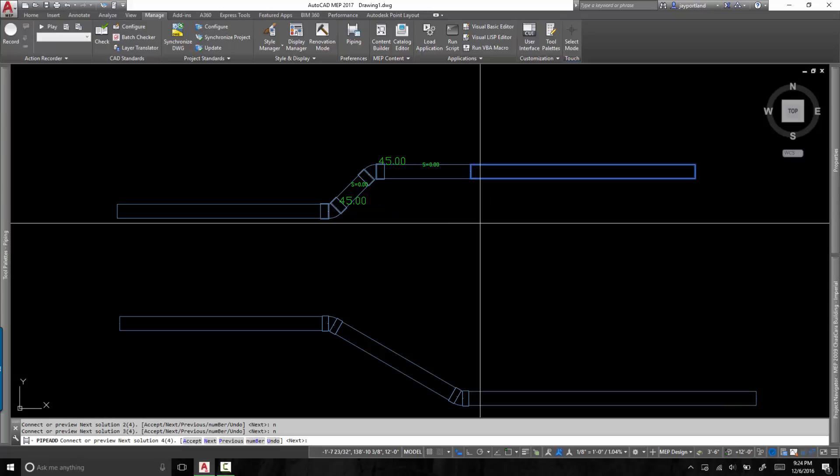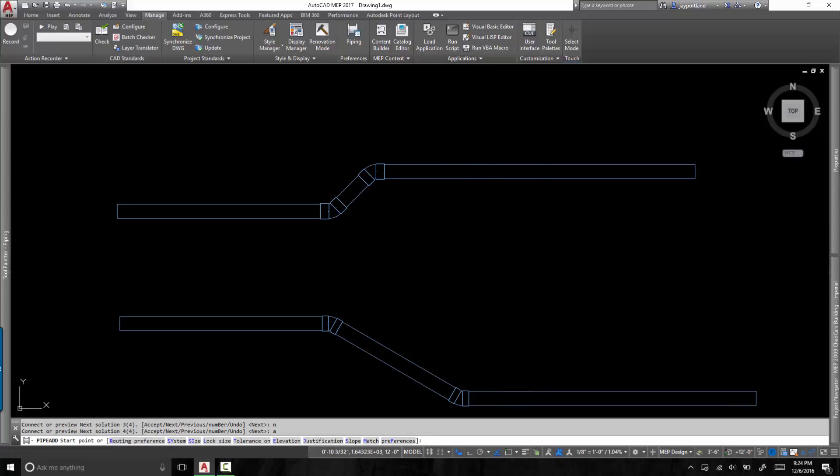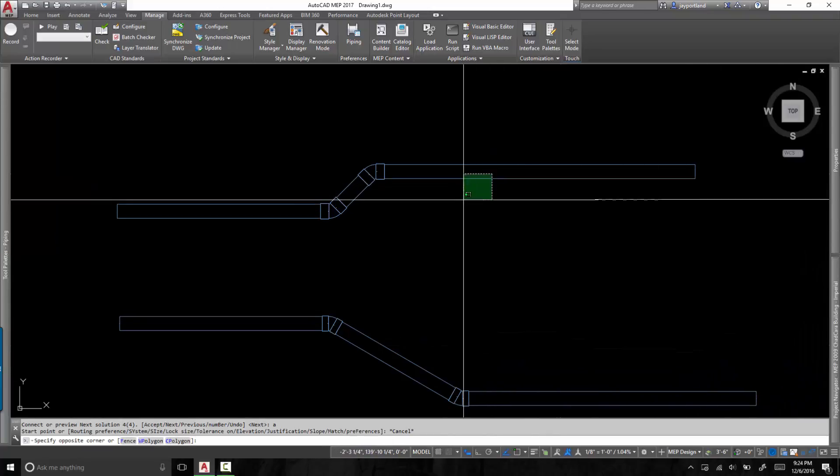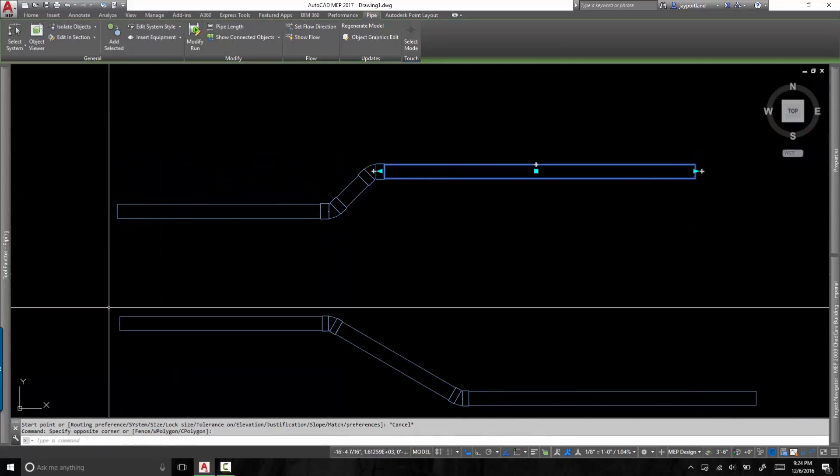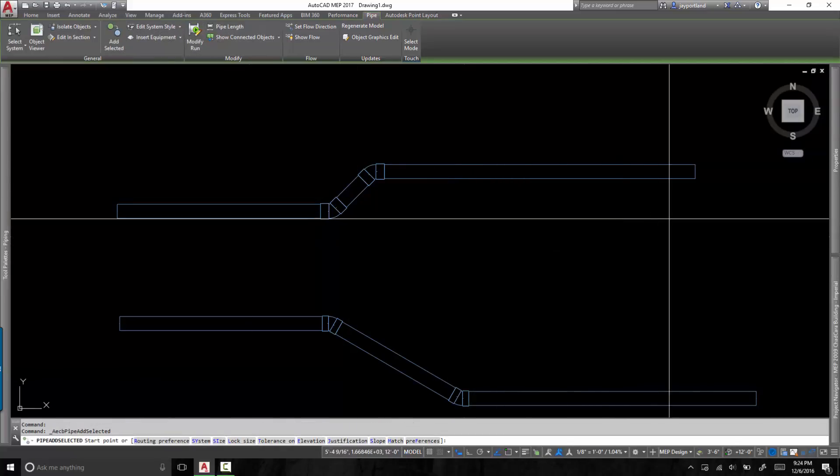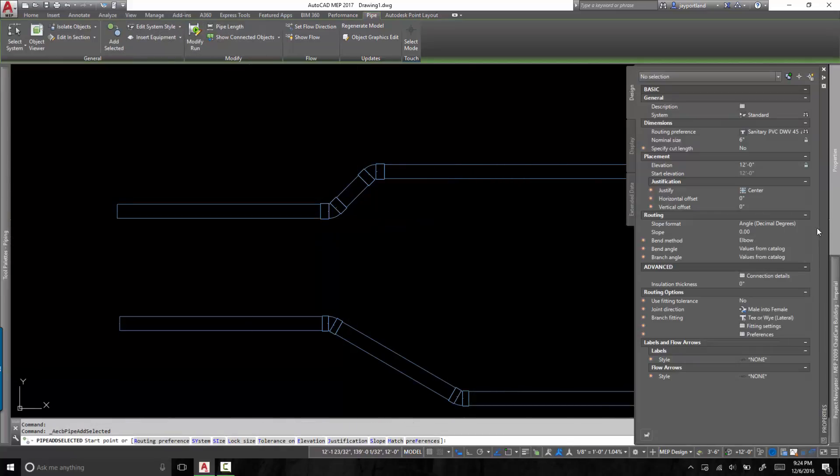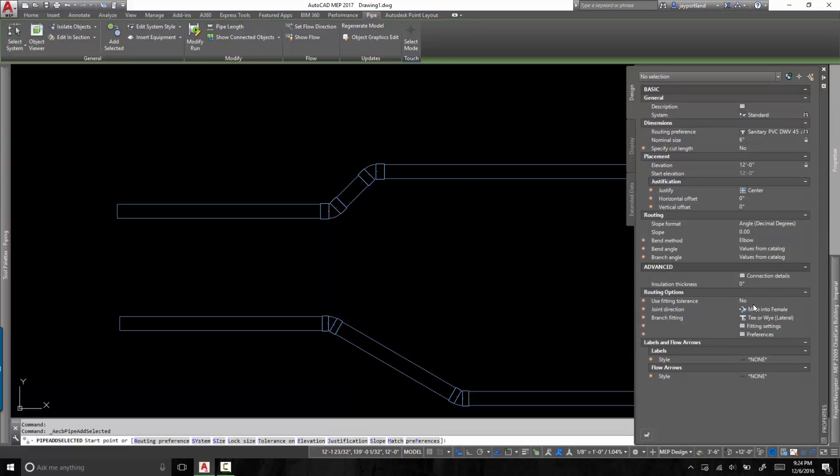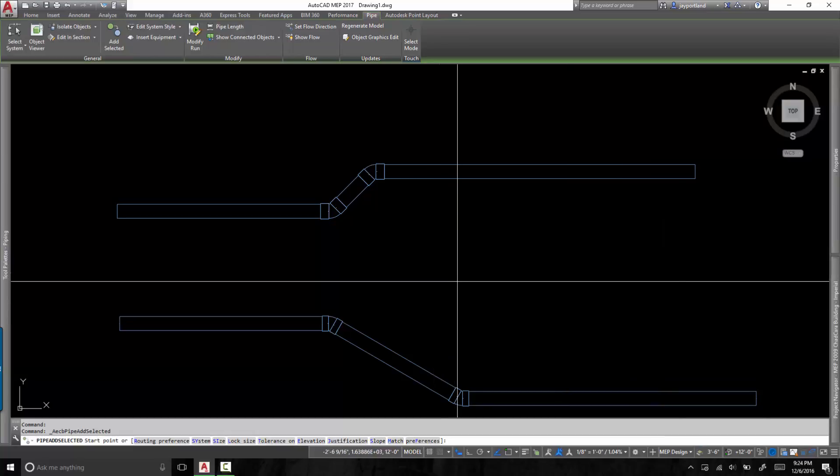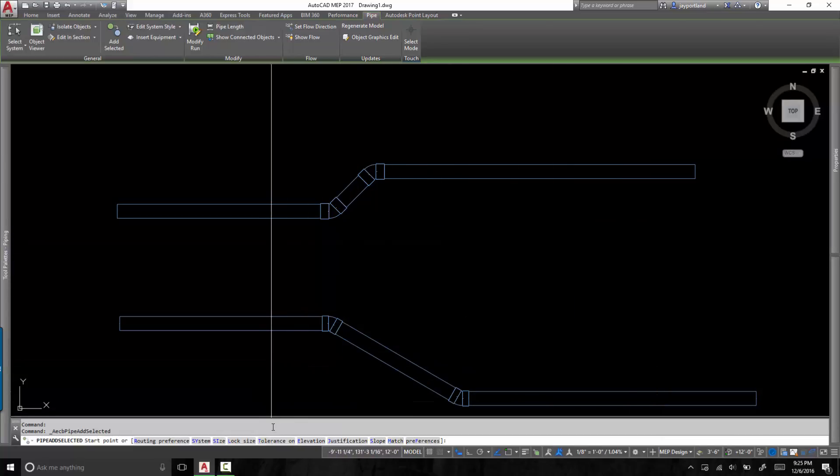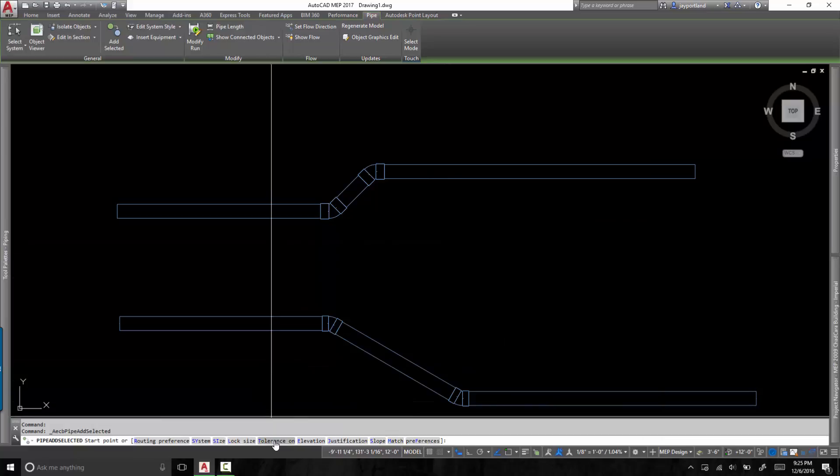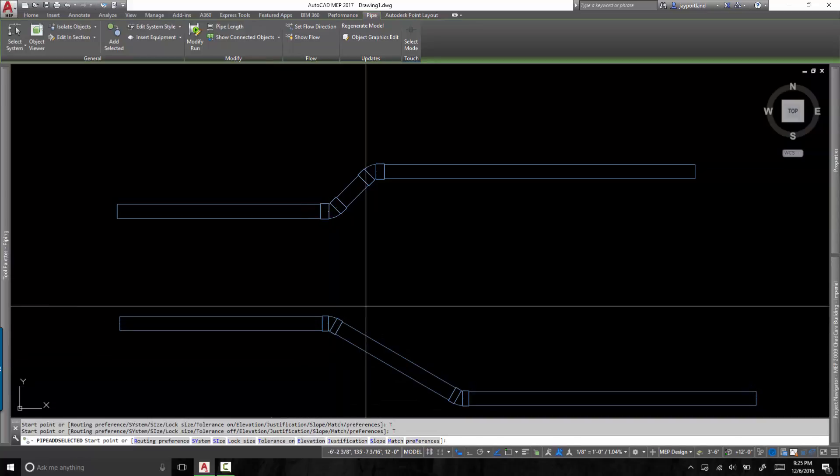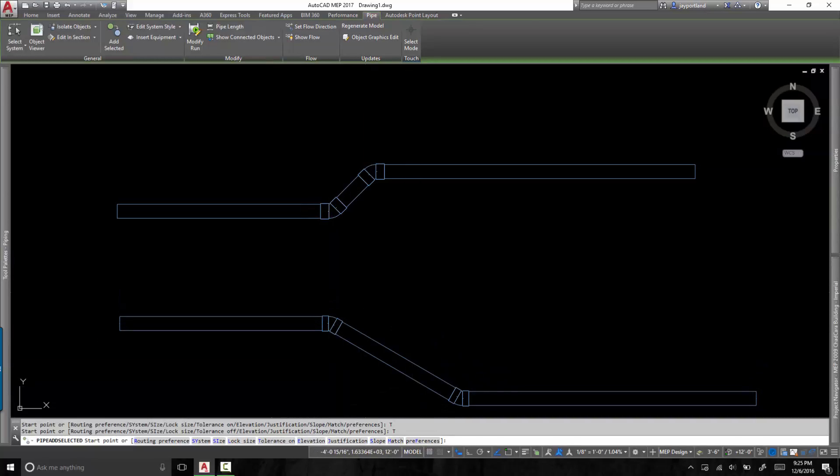All right. So in closing, what we did was we turned off a particular pipe routing feature. This can only be accessed once you've started the piping command in the properties palette. Okay. You will find it under the routing options. Use fitting tolerance. By default, it's on. I'm telling you to set it to no. And if you don't find it in the properties palette, you can also just turn it on and off in the command prompt under tolerance. So currently you can see that it's off. And if you click on this, it will turn it on. If you click on it again, it will turn it off. Right. So that's the first step.